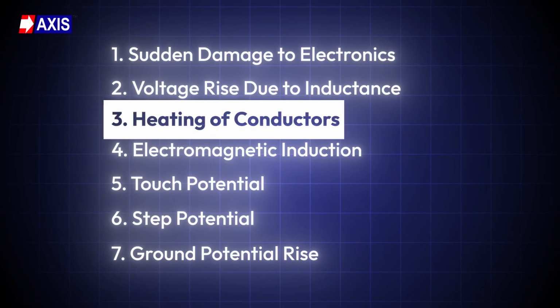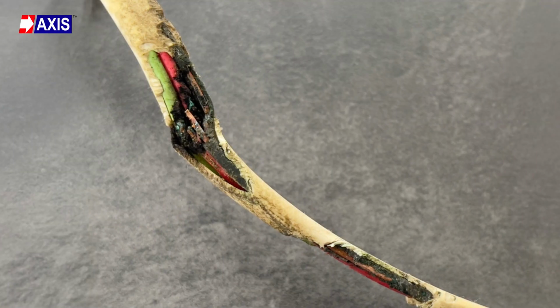Thirdly, heating of conductors. You will notice discolored insulation, a burnt smell near cables, or melted cable jackets. This usually happens near panels, bus bars, or long cable runs. This sign shows that a large surge current passed through the conductor, causing it to heat up very fast. Even if the cable looks fine from the outside, the insulation inside may be damaged.